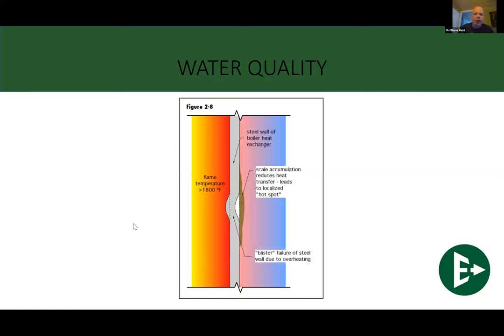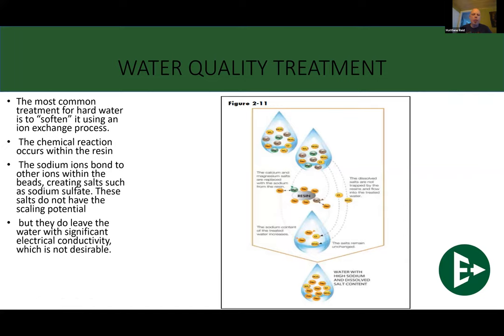So how do we get rid of the scale? The most common way to do it right now, that I see the most of, and it's not the best way, and I'll tell you why, is softening of the water. By running it through a water softener, essentially what you're doing is you're changing everything now to sodium ions. Now, these sodium ions, although they don't stick so much to metals, they don't have that scaling potential, we're now leaving the water pretty electrically conductive. So we're increasing that electrical conductivity inside the water. As we increase that, well, now we can start getting other problems inside of a system.